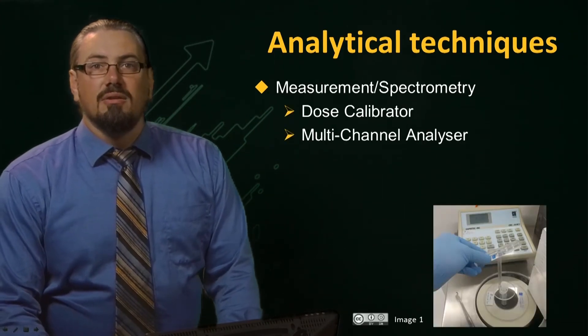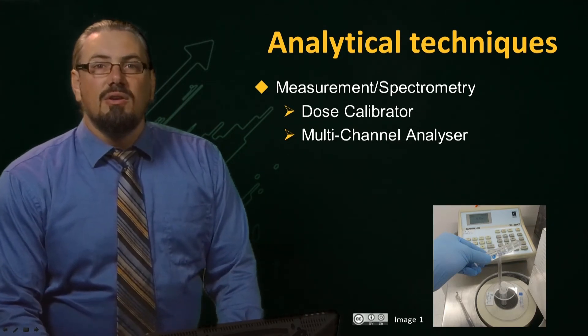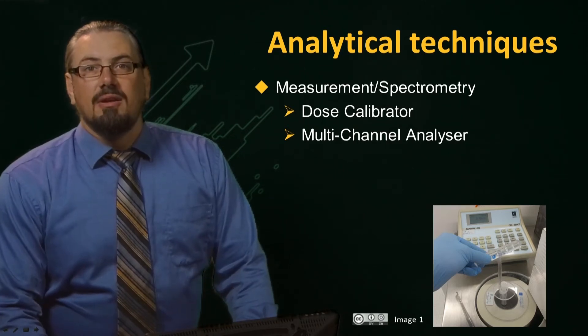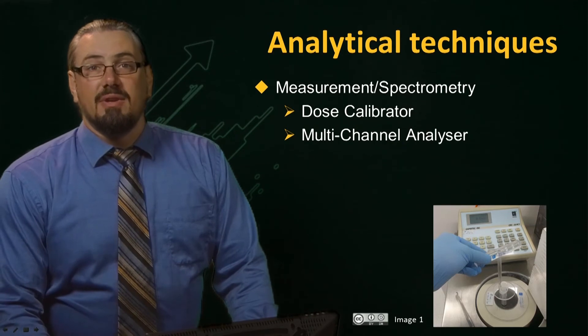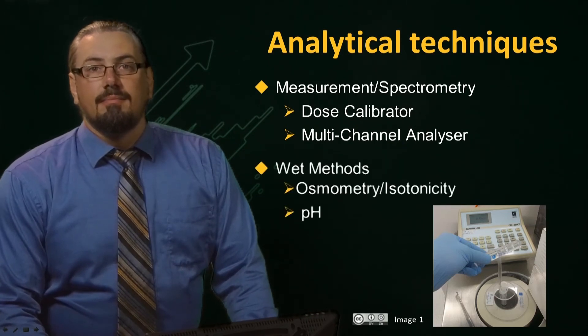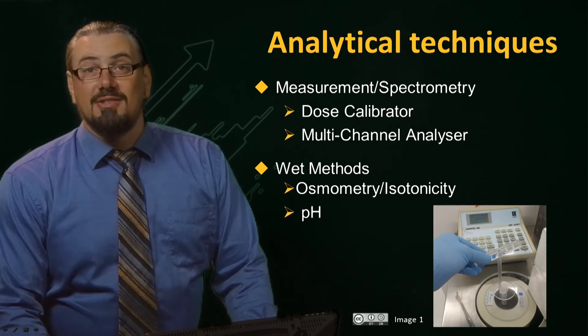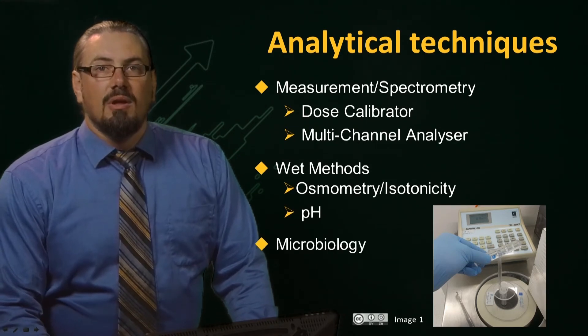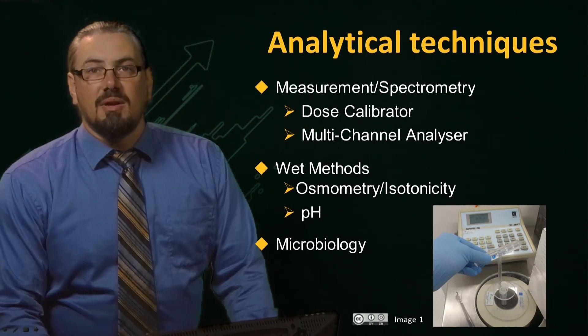In this section, you will gain an appreciation of how to test these product specifications using different test methods and analytics. Some of the techniques include measurement of the quantity of radioactivity present using a dose calibrator — Image 1 is a picture of a dose calibrator. Wet methods are employed for testing parameters such as isotonicity and the pH of the radiopharmaceutical preparation.